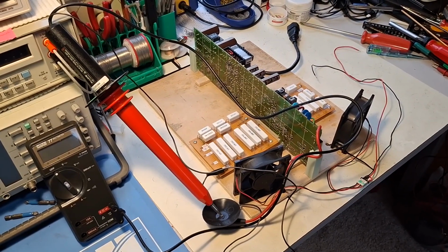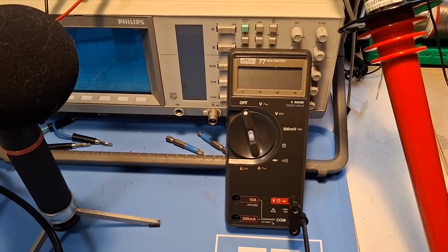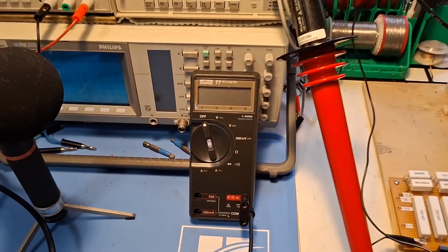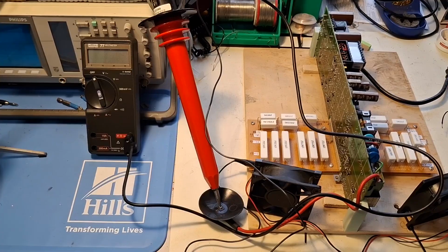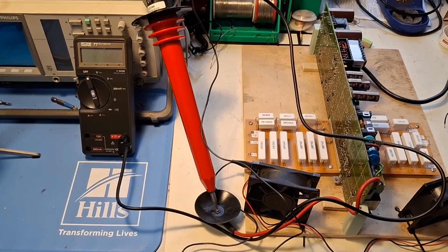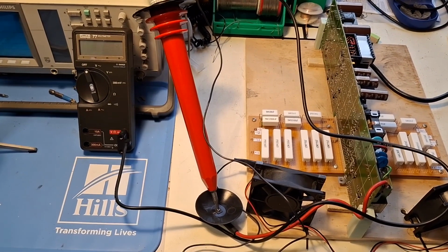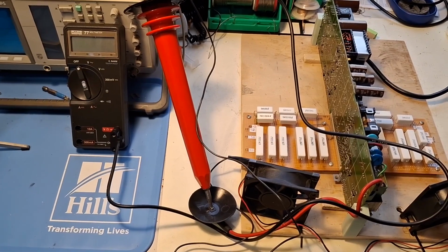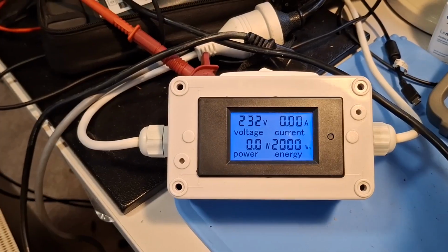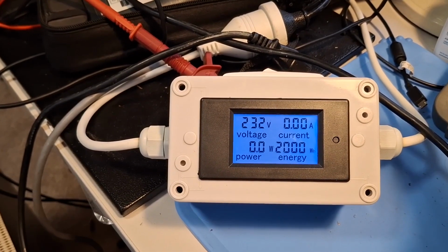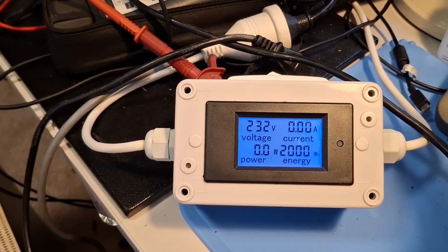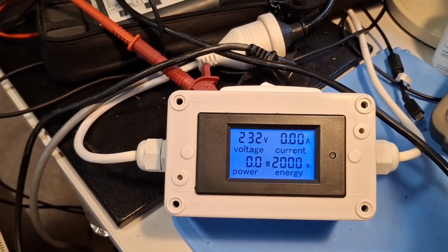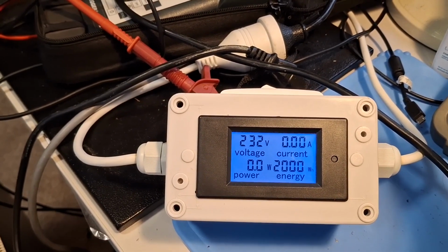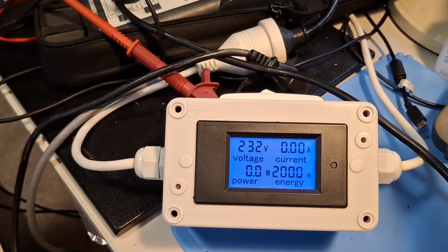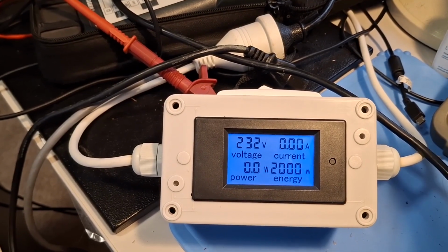The first test I'm going to do is look at the voltage output from the high voltage probe to ensure it's actually zero. If it isn't zero, I need to look at that immediately. The other reading initially will be the total power consumption, and for this power supply on the dummy load it should be about 115 watts. If I see more than that, I'll cut power immediately.